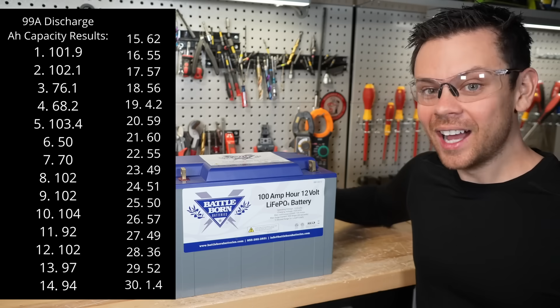Now all of that testing was at 49 amps charge and 99 amps discharge. So I lowered it down to see what would happen. In the last cycle I pulled 80 amps and got a lot more capacity, but it didn't trip the over temperature circuit and it melted the case. But realize all the problems I've been talking about is with the positive terminal—I don't even know what's going on under here.